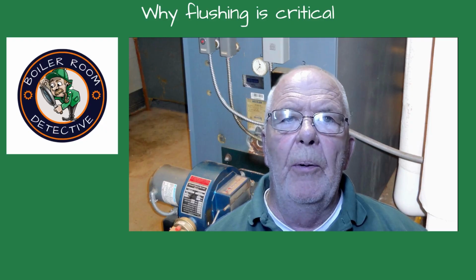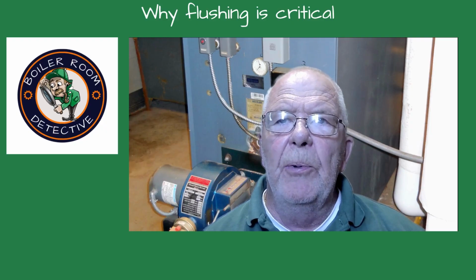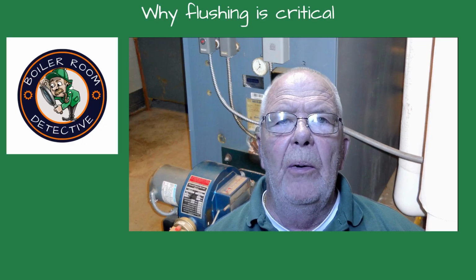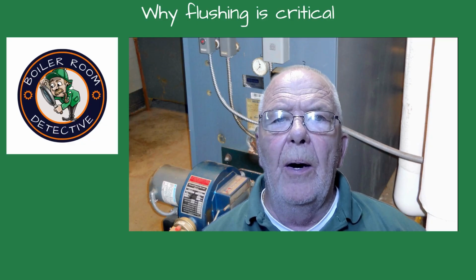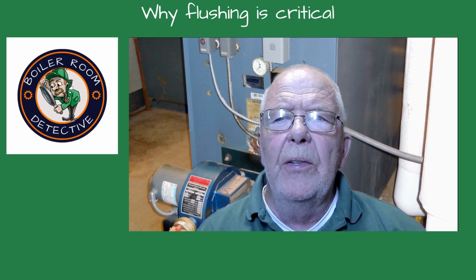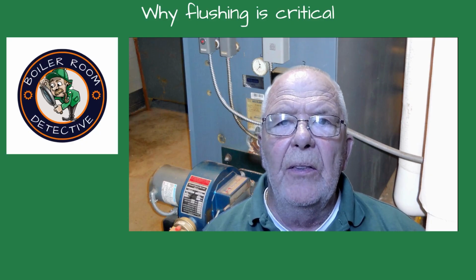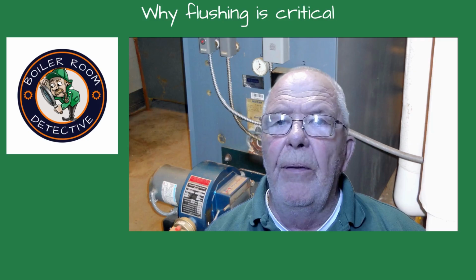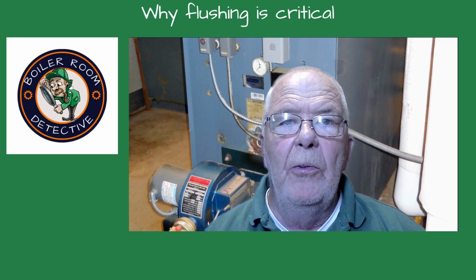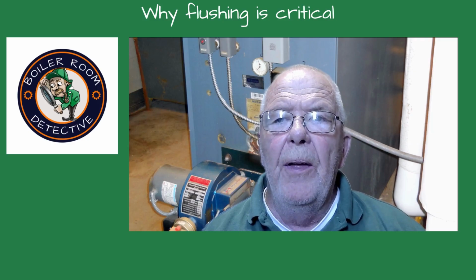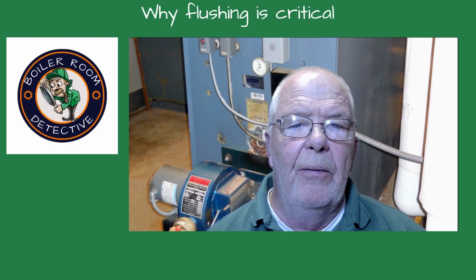You've been asked to quote on replacing this boiler. The customer said they would like a condensing boiler. You're going up against Low Bid Joe and looking for an edge to get the job. You could use the work. You think to yourself, if I don't drain the system and reuse the system water, think of all the hours I would save from venting air. That would be a huge mistake, my friend. I'm Ray Wohlfarth, and this is Boiler Room Detective.